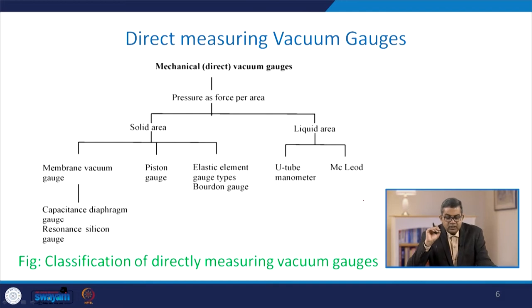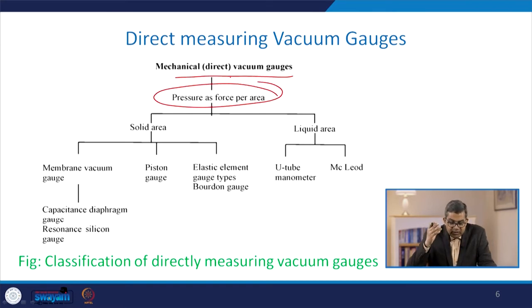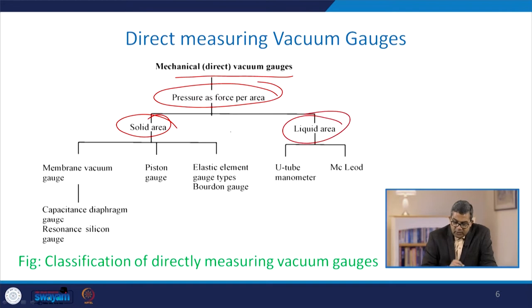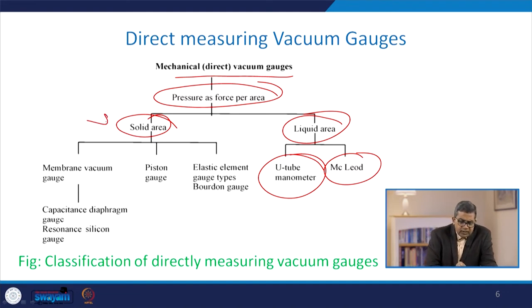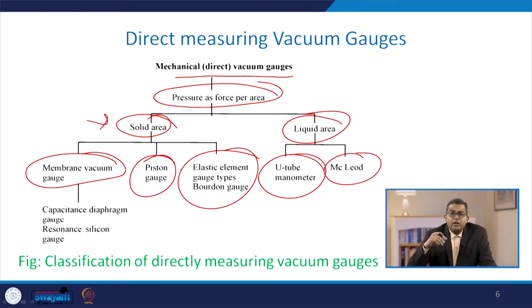Mechanical or direct vacuum gauges represent pressure as force per area and can be subdivided into two categories: liquid area and solid area. In the liquid area, there are the U-tube manometer and the Macleod gauge. In the solid area, there are the membrane vacuum gauge, the piston gauge, and the elastic element gauge type or Bourdon gauges. The membrane vacuum gauge is also referred to as the capacitance diaphragm gauge or resonance silicon gauge.